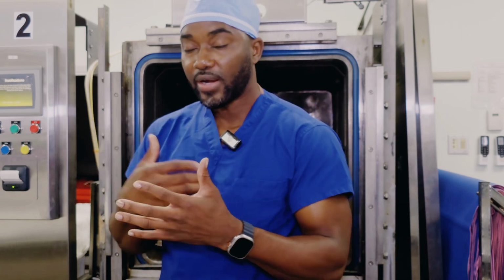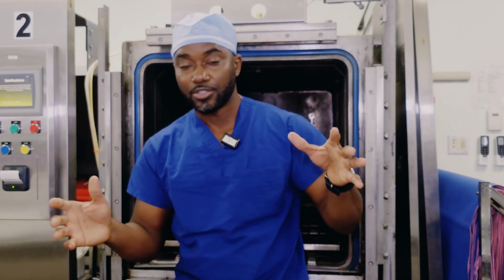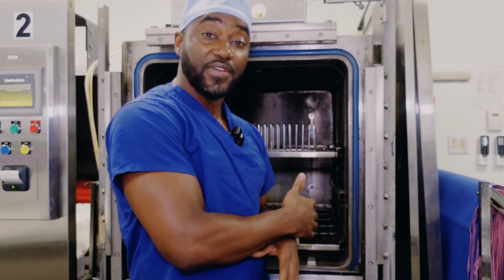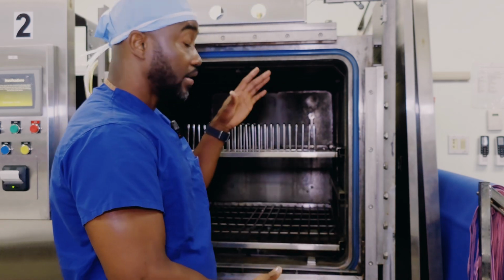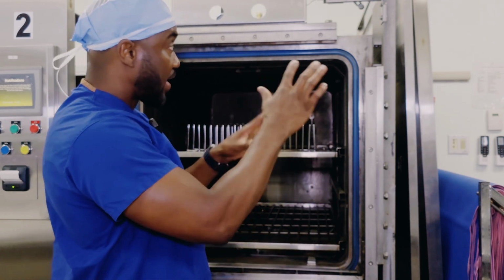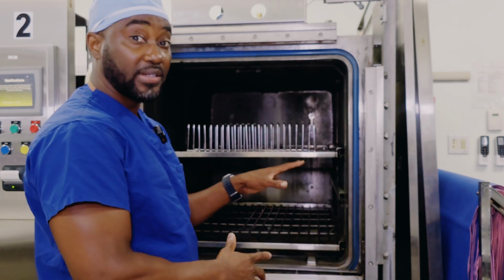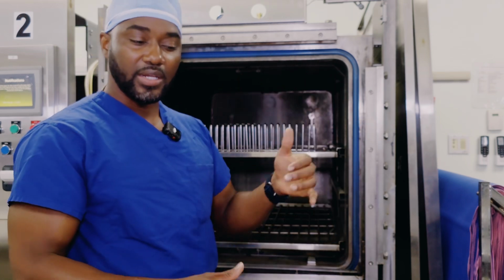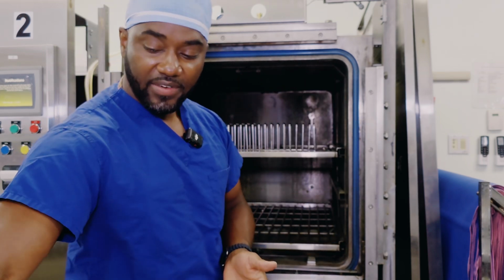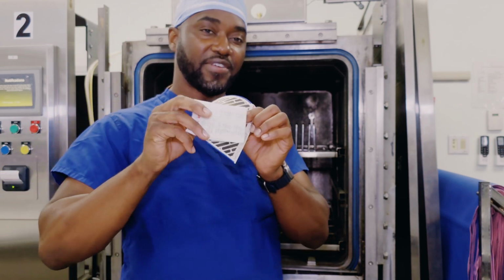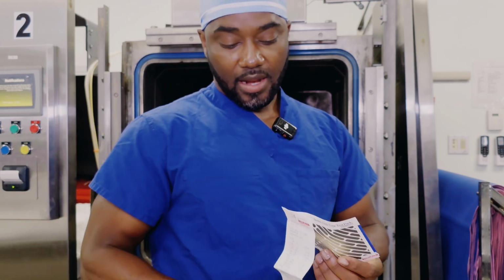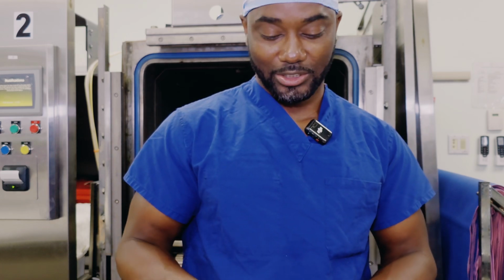After you do that, you have to record everything. For sterilization, record keeping is mandatory and not optional. You have to record the good, the bad, and the ugly. We have to record that our load failed, and we have to do another quality test after. Right now, this machine is shut down for maintenance, for repair, because we called it in for repair because we have our Bowie-Dick test failing today. So that's enough information on your quality testing or your quality assurance test.